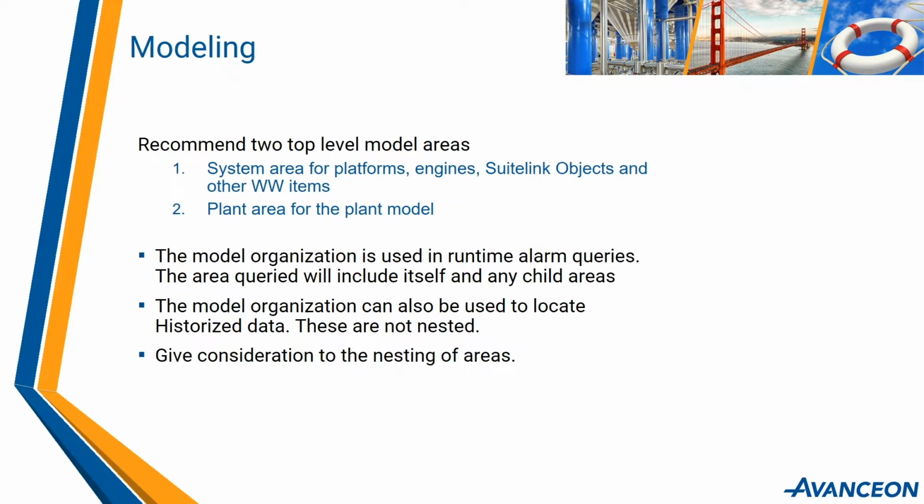So another comment on modeling. We recommend 2 top-level model areas. One's for the plant and the other's for just a system area for platforms and engines and all that other good stuff. So within your plant area, you want to add contained areas according to the logical organization of the plant. This organization is used for running runtime queries.